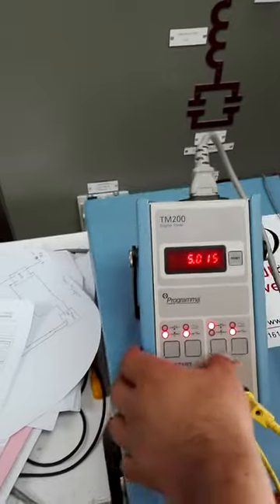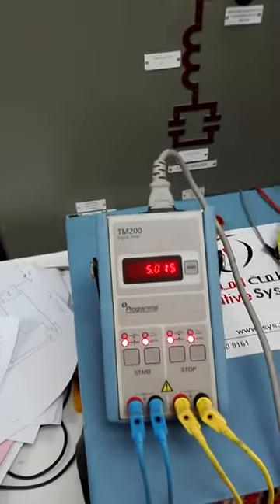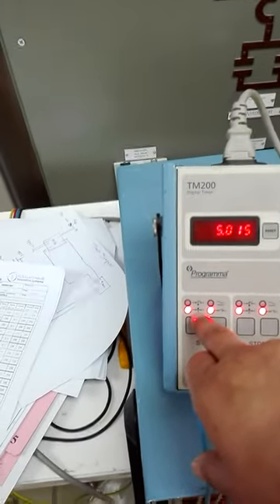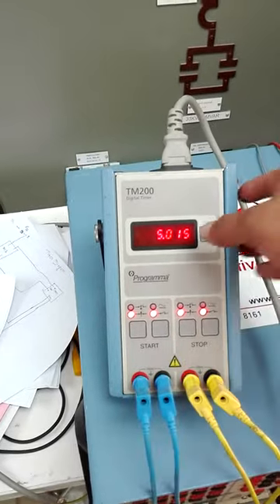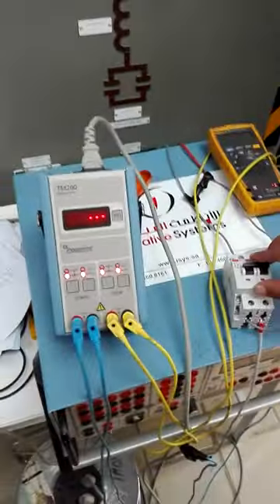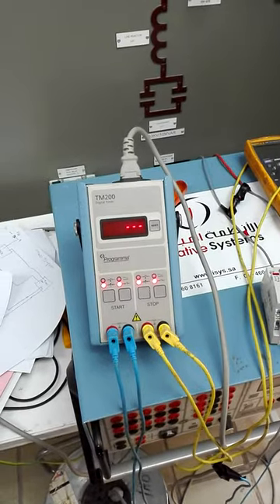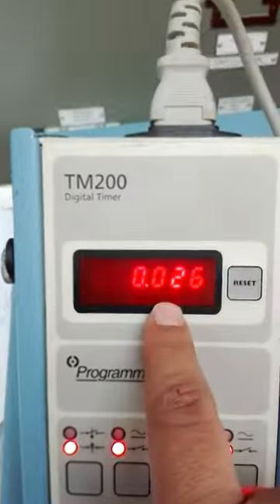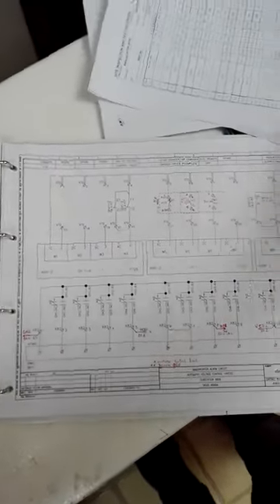Now for the reset time delay measurement, I will do the same from normally closed to normally open, and we will measure the time. Reset and then on, same delay, approximately equal to 5 seconds. You can see it from the table. So if you understand this pattern, we will follow the same pattern and just measure the time.